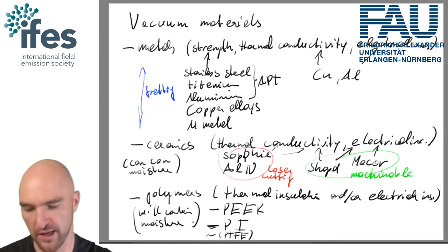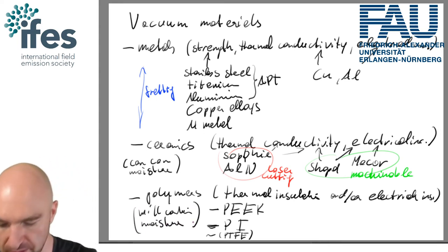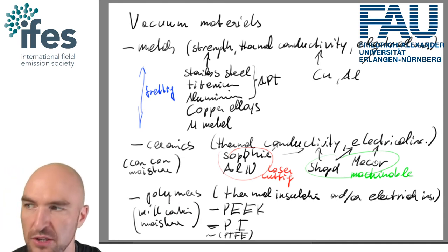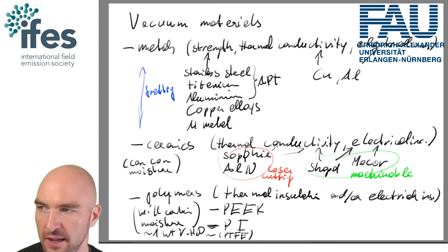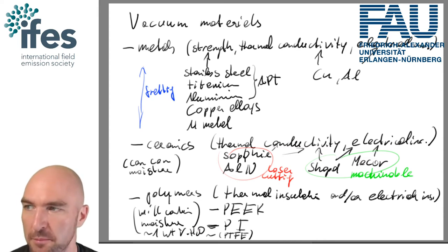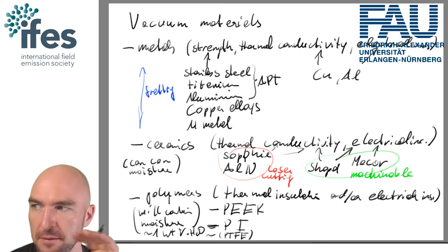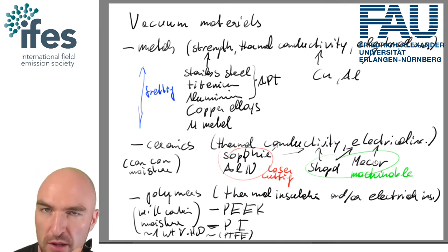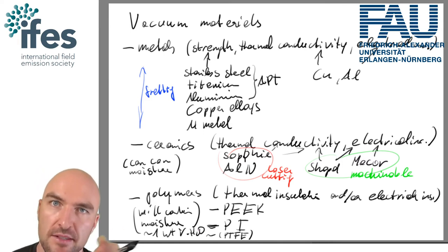So in terms of ultimate vacuum performance, polymers are actually not that bad. The problem with them is they will take up around 1 weight percent water vapor at room temperature. So they're hygroscopic, so at ambient pressure, if you leave it out before you put it in, it will pick up about 1% of water vapor.